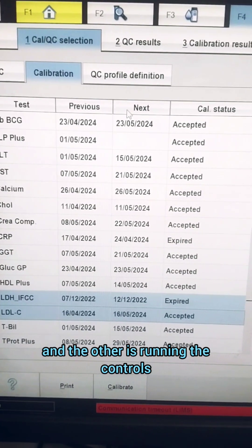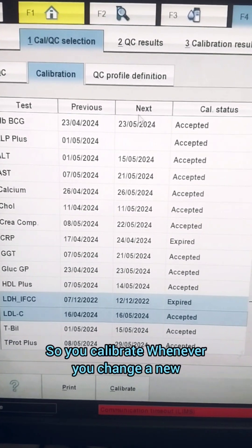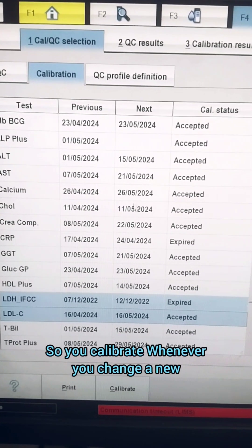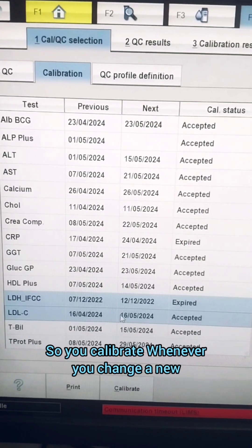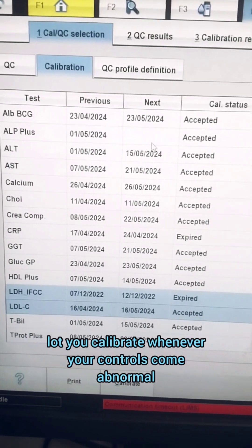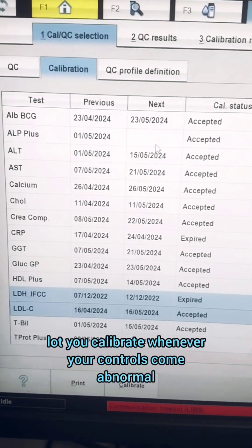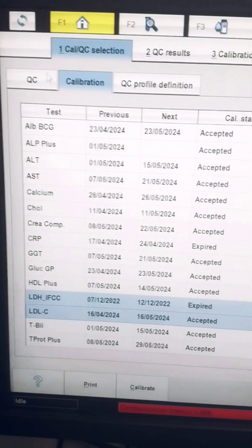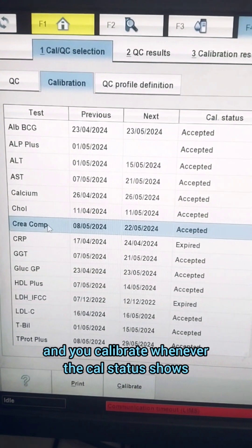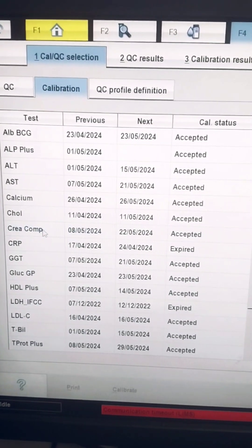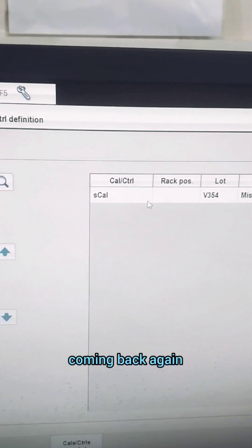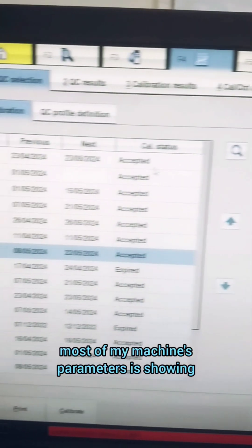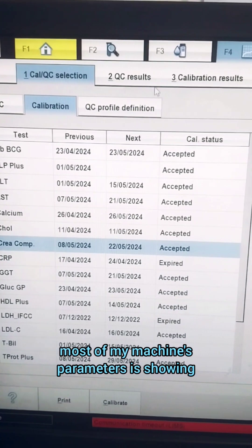You calibrate whenever you change a new lot, you calibrate whenever your controls come back abnormal, and you calibrate whenever the cal status shows that it's expired.